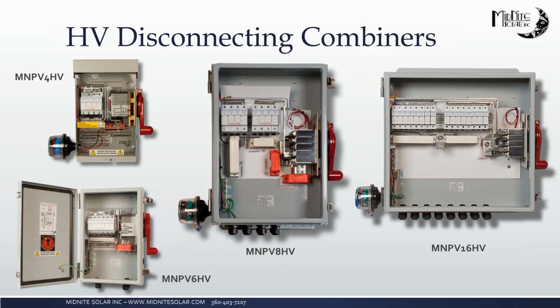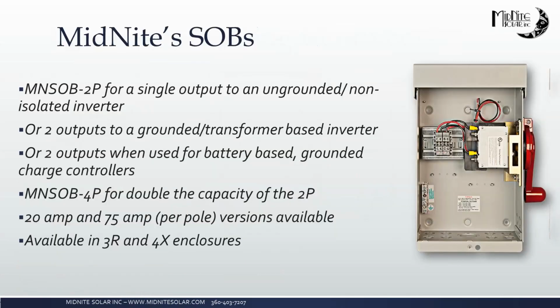So you can configure this for, say, 8 strings into a single inverter, 1 positive, 1 negative out of the box. You could do 4 strings in and 4 strings in, isolated, and do 2 negatives and 2 positives out of the box. It could go to 2 separate inverters. Or you could do 4 positive and 4 negative in out to a single transformerless inverter. The PV16 is exactly the same, just twice as much fun. So you could do 8 strings to 2 separate inverters, 16 strings to a single inverter, or 8 positive, 8 negative to a single transformerless inverter. These are all available with the PSB, which I believe we talk about a little bit later, so I won't go deep into that right now.